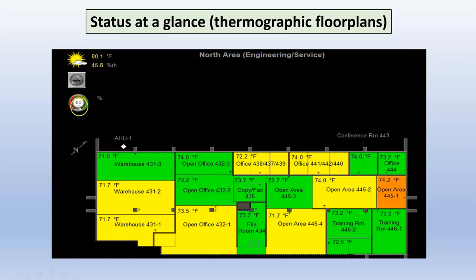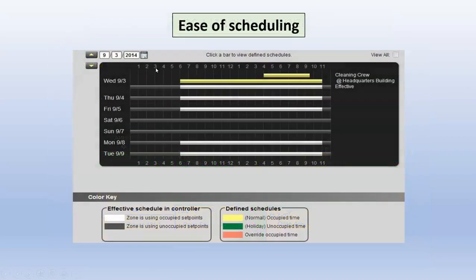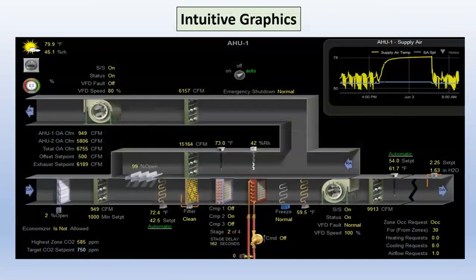If you look in the upper left-hand corner here, you can see that we actually have our outside air parameters on there. Another real easy thing to look at. This is the schedule. I can look right away and see if something's scheduled. This is a good graphic screen of an air handler. Notice that just about everything you want to know about that air handler is on there. I got CFM, I got temperatures, modulation. There's just so much stuff on here. Even have a graph that shows me the supply air. I can see if it's got a reset, which looks like it does, where it changes temperature based on outside air temperature.